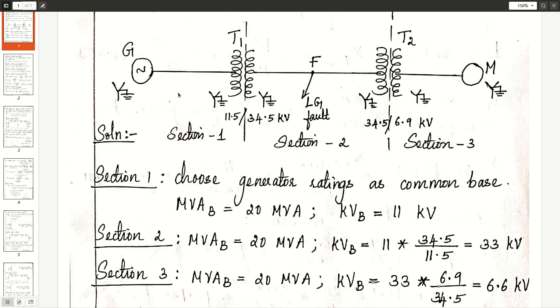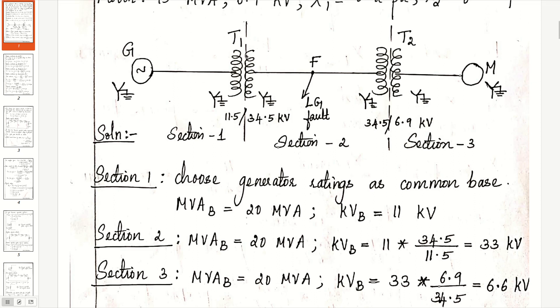Let us consider generator ratings as the common base. So MVAB is 20 and KVB is 11. Section 1 is the generator section. Based on the transformer, we divide the transmission network into three sections. In section 1, generator ratings are chosen as the common base. In section 2, MVAB remains the same at 20. KVB is equal to section 1 KV into transformation ratio of T1, which is 33 kV.